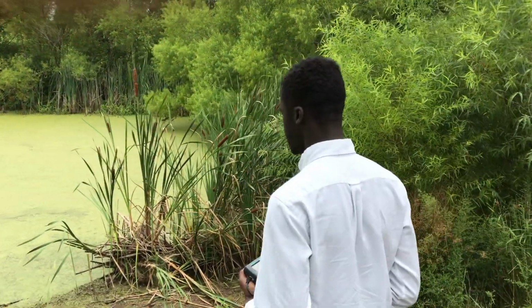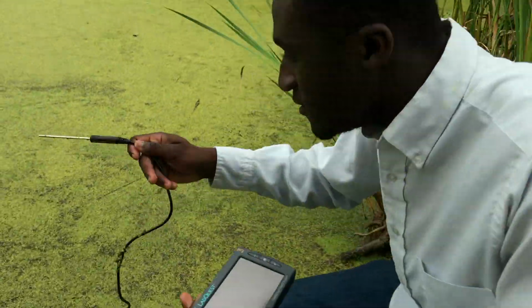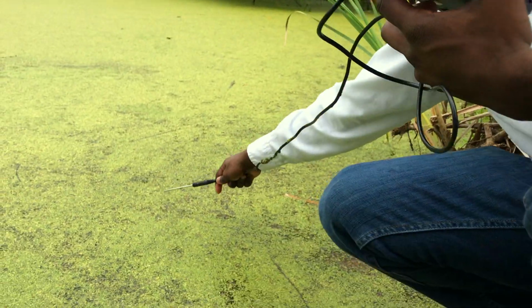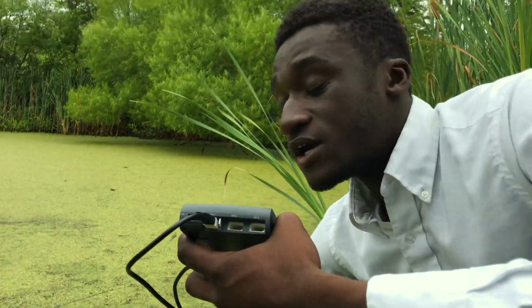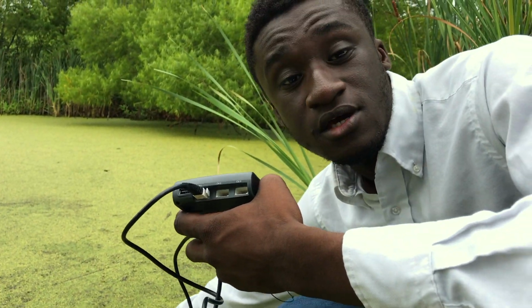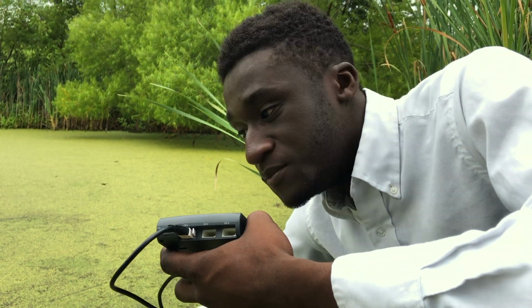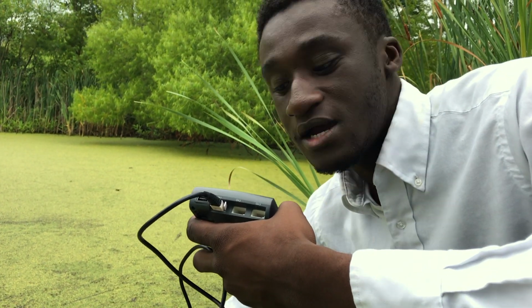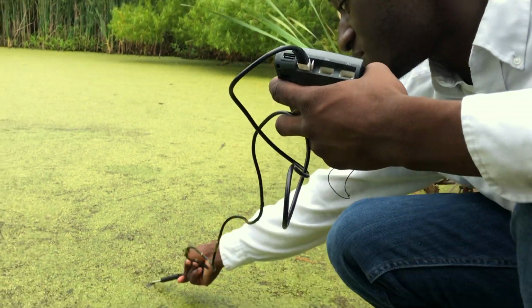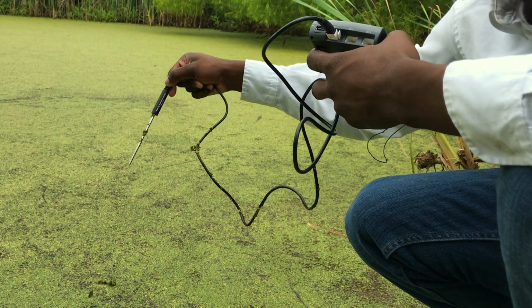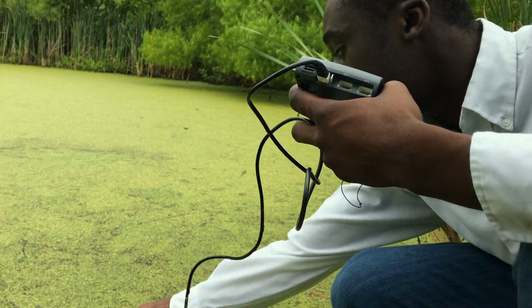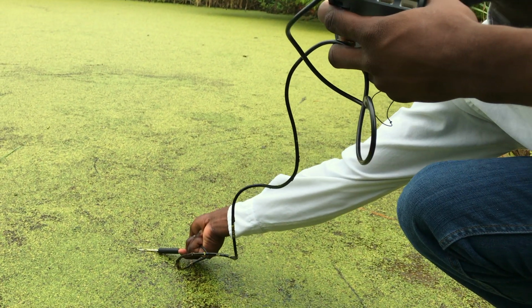Let's find the water temperature. All right, now we can get right into testing the water. Down here, and get in there. You don't need to get directly into the water, but you just need to make sure that you're not touching, ideally, any mud or any of the algae or anything that could be around it. So you get the temperature of the actual water rather than any of the gunk like this that might be around it. So we're going to try to lay it down a little bit here, make sure we're only touching water.